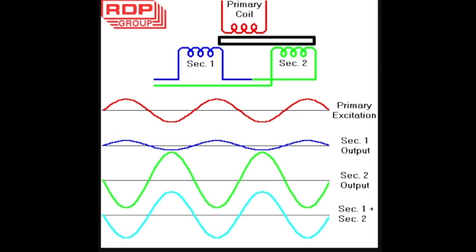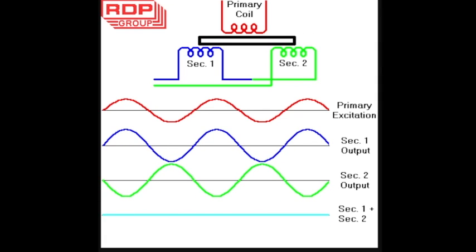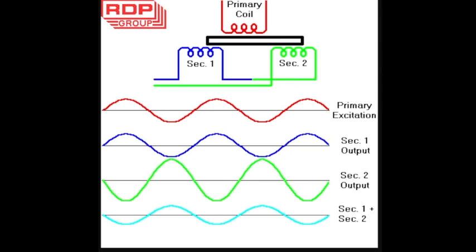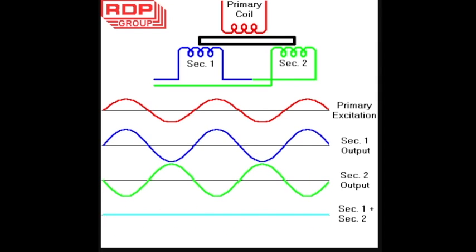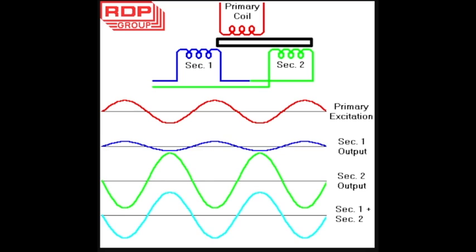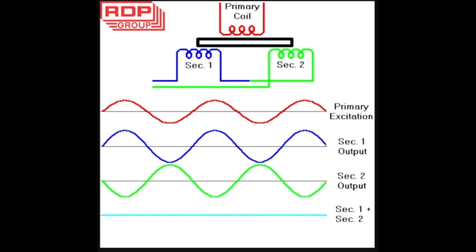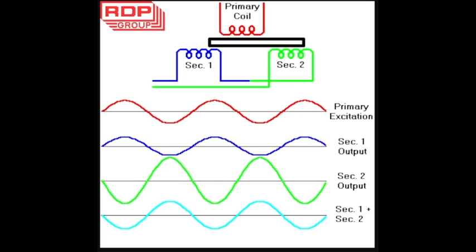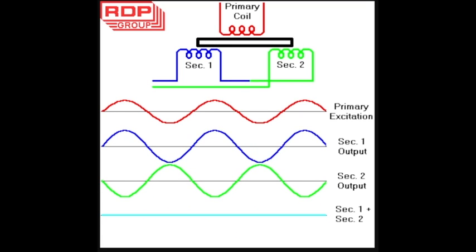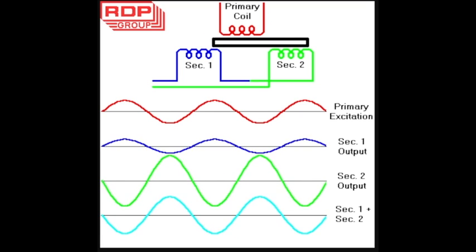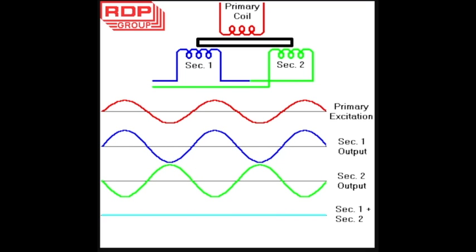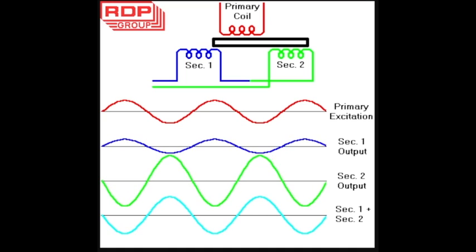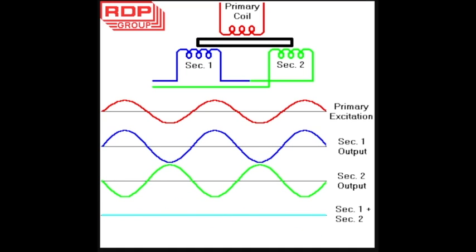An LVDT typically consists of an iron core moving relative to an outer cylinder which houses a primary coil and two secondary coils. The primary coil is being driven by an alternating current which induces a magnetic field on the iron core, which is similarly alternating, and therefore, per Faraday's law, would induce currents on secondary coil 1 and 2. Depending on the number of turns linked between the secondary coils and the primary coil and the iron core, the voltage signal will change between them.